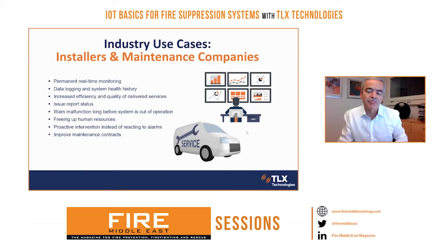There's also the other aspect, which is preventing systems from going out of service because of a failure. I want to mention a specific case that adds a lot of value for installers and end users: early detection of failures, or micro leak detection. Imagine you're monitoring pressure and temperature, or liquid levels through an electronic liquid level device. Today we're able to measure not the 5 or 10% that the standards request, but deviations of 0.1%. And if that measurement repeats in the next hour or the next day, we can confirm there is a micro leak in that tank.